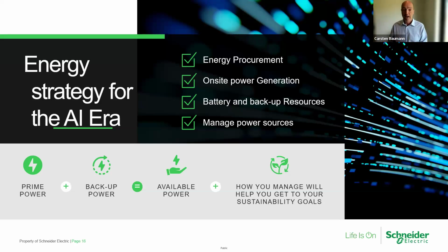Is it bridging power? So where a data center operator wants to have 100, whatever 100 is, or maybe, let's say, megawatts, but the utility company can only give them 20. So how do I make up the 80 today? However, tomorrow the utility company may say, look, we're upgrading our infrastructure, and now instead of delivering 20, we can deliver 40. So now I had to fill a gap of 80, but tomorrow the gap's only 60, then it might be 40, then it might be 20. So we have to think about these creative strategies, and that feeds right into the backup power strategy.